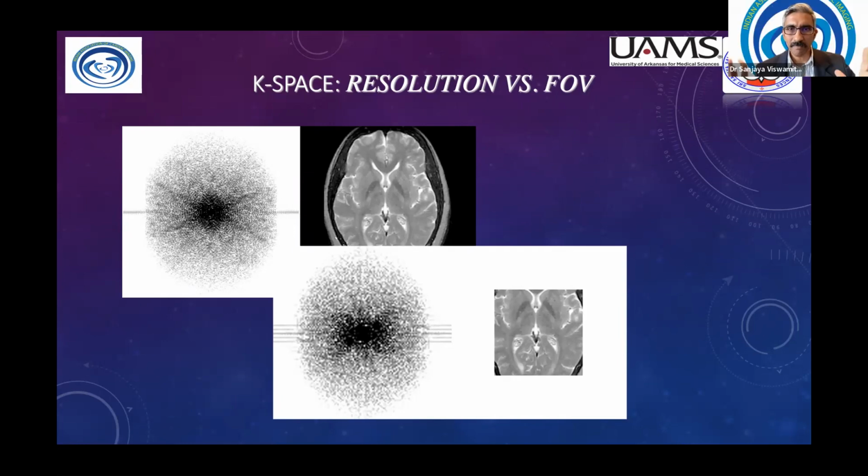Okay, same story. You need to fill up your K space to get an image. Let us say the K space for a particular cardiac image needs 128 phase encoding steps. You can fill up the 128 phase encoding steps as two big blocks of 64, right? Two simple big blocks of 64 can be used for that particular thing. Now, those are two segments.